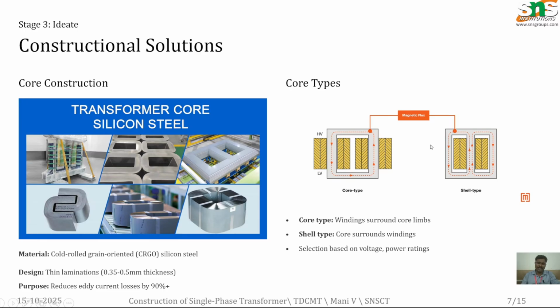In the shell type transformer, there are three limbs, and both the primary and secondary windings are mounted on the center limb. The core type transformer has only one magnetic path, but the shell type transformer has two magnetic paths. The core type windings surround the core limb.